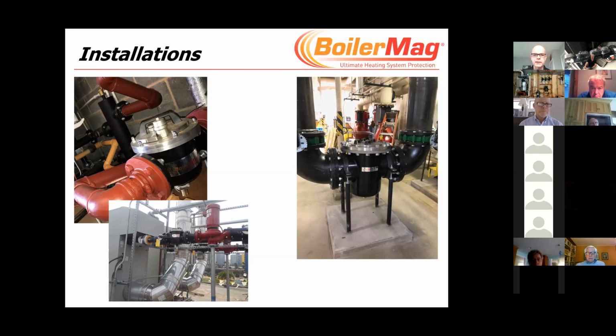When you come to clean it, the easiest way is to pull the magnets out and drain it out of the bottom, so you don't have a big disassembly job. If you don't do that and remove the entire top assembly with the magnets still in the cartridge, that's what it looks like - so you can see what you've collected. Most people want to do that on the first couple of cleans, so they can see how bad their system is and how often they'd need to clean it.